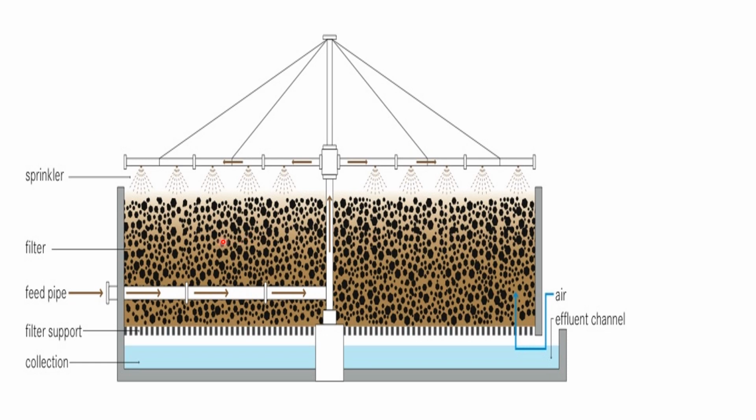And this is the filtering medium. Filtering medium is mainly made up of broken bricks, crushed rocks, charcoal, and dried leaf, etc. And this filtering medium mainly contains the aerobic bacteria. The filtering medium is the source of aerobic bacteria. So these are the main parts of trickling filter.